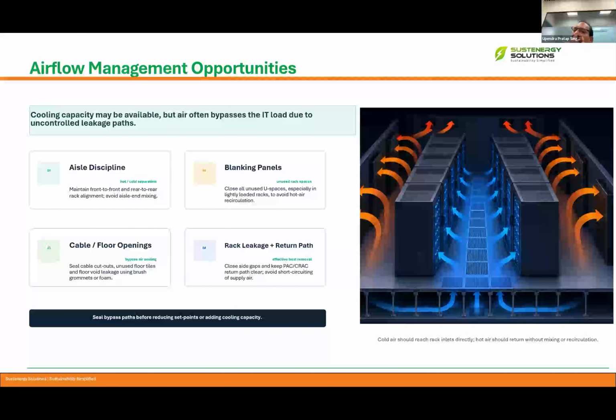This is one of the things, and many people are now installing containments and maintaining hot aisle, cold aisle arrangements. The second very common observation in airflow management is blanking panels. Many times we observe that they don't put in blanking panels, and cold air passes through the rack directly and mixes with the hot air, effectively increasing the temperature. So we need to close all the unused U spaces, especially where the rack density is high, so that we can avoid hot air recirculation. This is one of the areas.